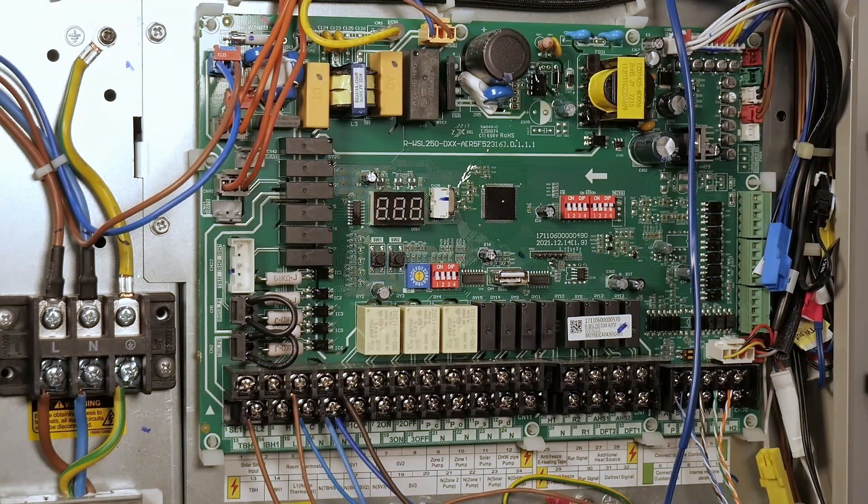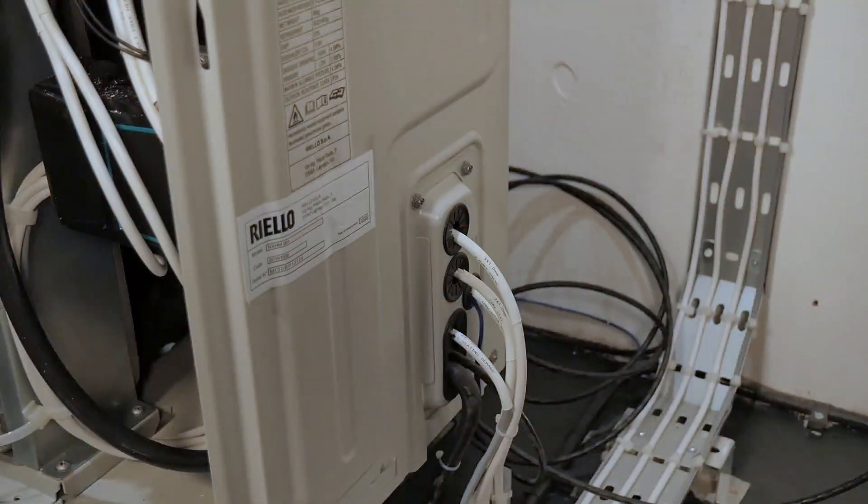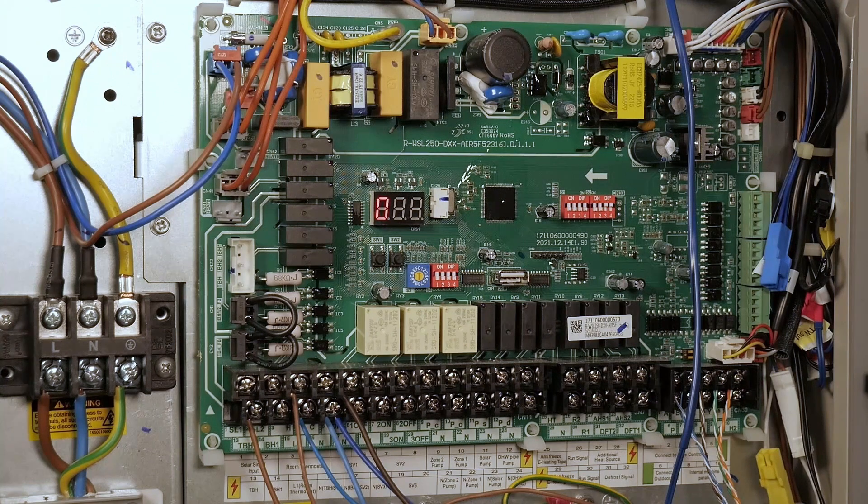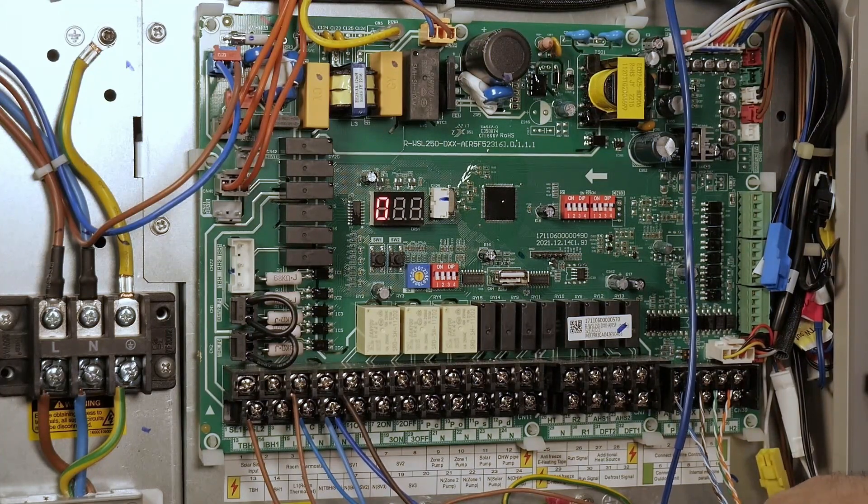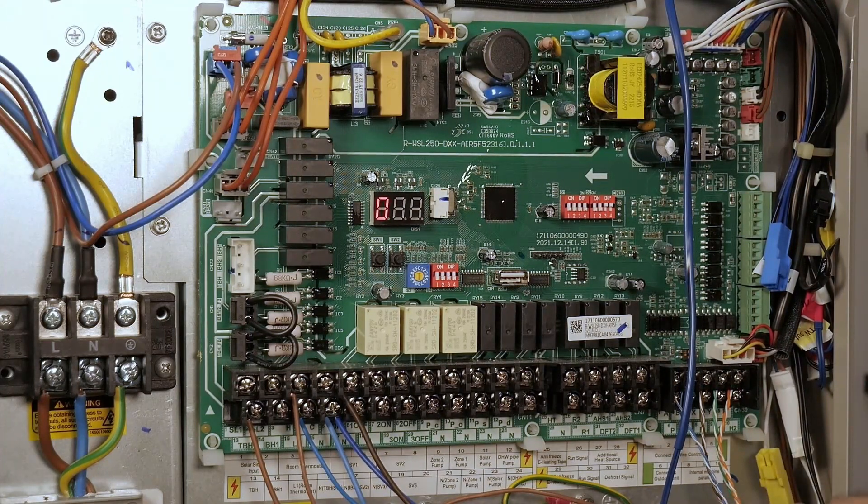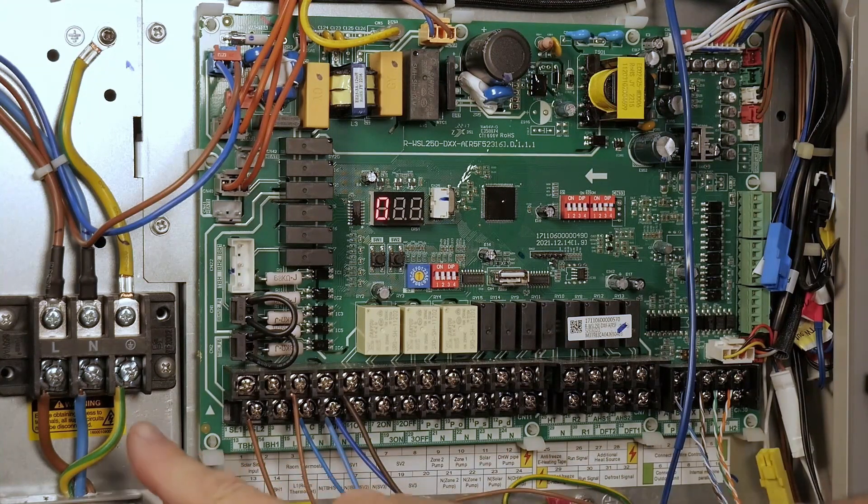Okay, electrical overview inside this Riello monoblock. Bringing the power through the side of the chassis, it has rubber grommets there. You must keep the high power and low power cables 50mm away from each other. These are passing up through the bottom here from the lower part of the chassis into these cable clamps, and your incoming power here as well will be brought in. This is where your main electrical feed is brought into this terminal block here.